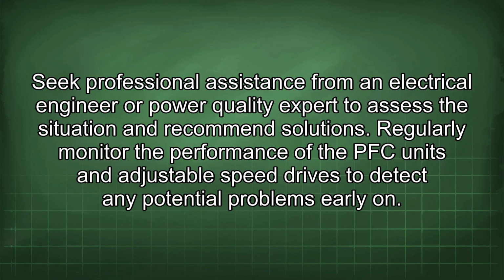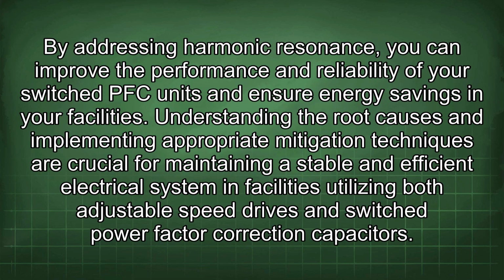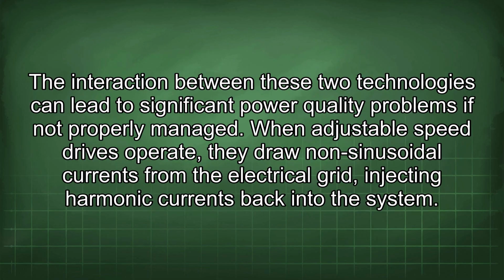Regularly monitor the performance of the PFC units and adjustable speed drives to detect any potential problems early on. By addressing harmonic resonance, you can improve the performance and reliability of your switched PFC units and ensure energy savings in your facilities. Understanding the root causes and implementing appropriate mitigation techniques are crucial for maintaining a stable and efficient electrical system in facilities utilizing both adjustable speed drives and switched power factor correction capacitors. The interaction between these two technologies can lead to significant power quality problems if not properly managed.